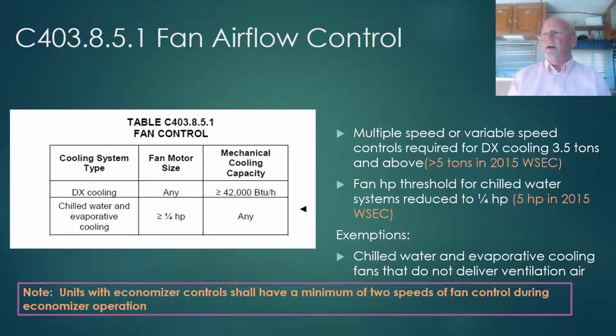And then also on chilled water systems, the fan motor size limit has been reduced from 5 horsepower to 1/4 horsepower for chilled water. So variable speed or multi-speed fan controls are required. And then finally, if you've got a unit with an economizer, the economizer is required to have a minimum of 2 speeds of fan control during economizer operation.